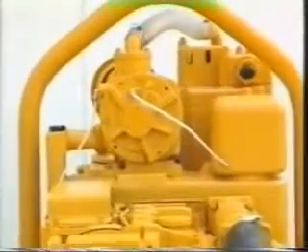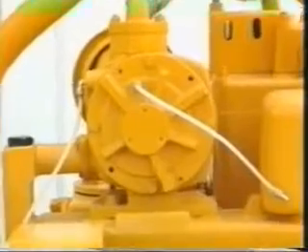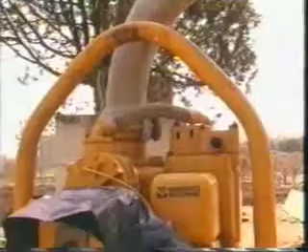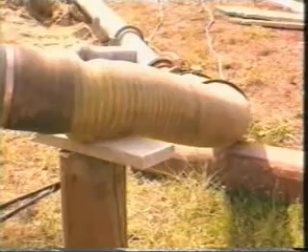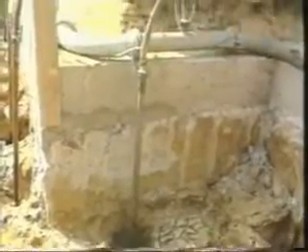As the pump well point circuit is in a vacuum, it must obviously be airtight. Even if air leaks from the joints and pipe fittings, however, operation is nevertheless ensured by the high air expulsion capacity of the vacuum pump. The plant suction pump must above all provide for a continuous expulsion of air due to the leaks in the system, or, in the case of soil with poor permeability, simultaneous absorption of air and water through the individual well points.